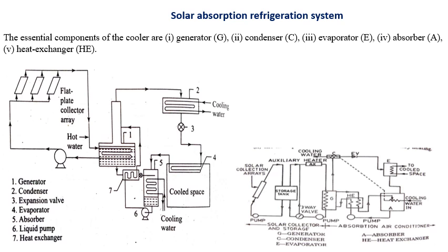Okay, so the coolers used in most experiments today are lithium bromide water cooled absorber and condenser. The pressure in the condenser and generator is fixed largely by temperature drops across the heat transfer surfaces in the generator and condenser.